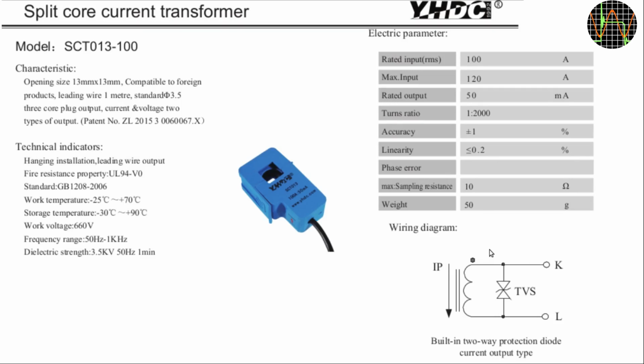It basically shortens the secondary before the voltage spikes get to a dangerous level. And while we're at the datasheet, I want to point out a few things. The rated input is 100 amps, which produces 50 milliamps based on the ratio of 1 to 2000. The accuracy is actually quite good, with ±1%, which beats the Uni-T, for example.